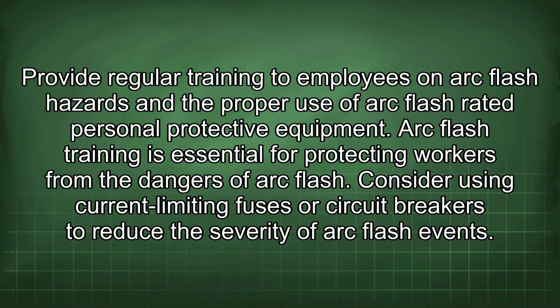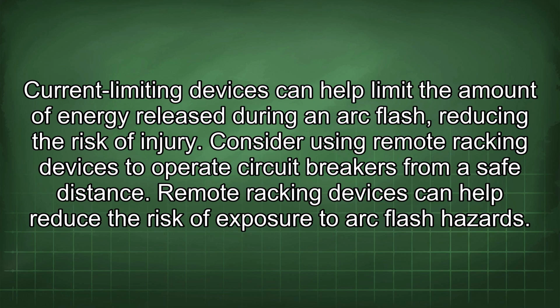Consider using current-limiting fuses or circuit breakers to reduce the severity of arc flash events. Current-limiting devices can help limit the amount of energy released during an arc flash, reducing the risk of injury.